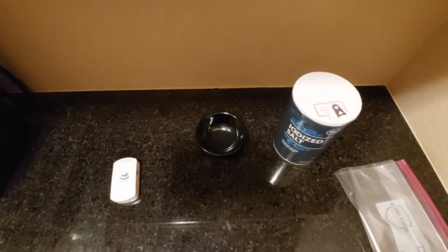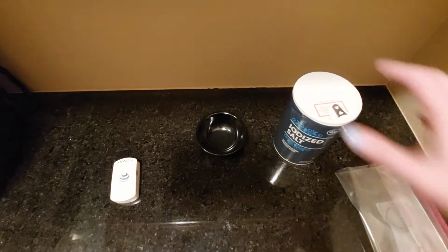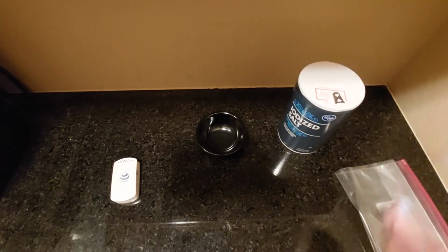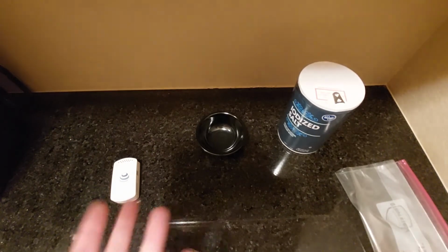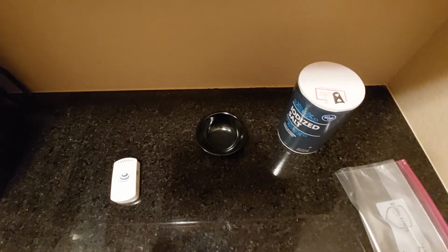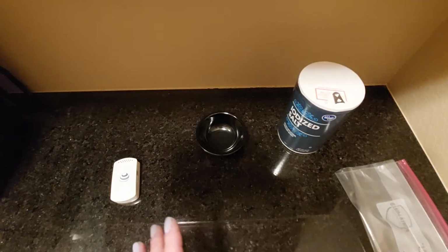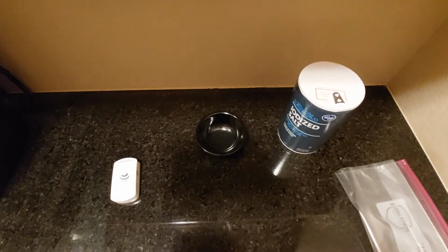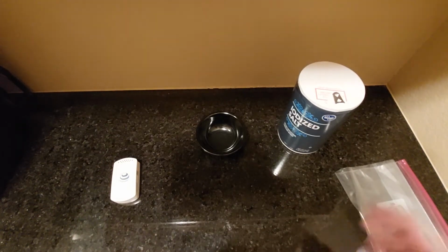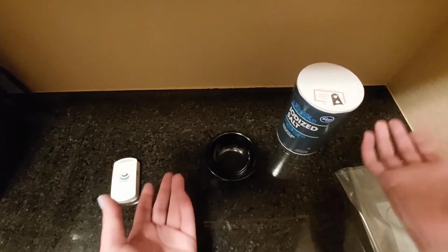So next we're going to review how to do a 1-point calibration test for relative humidity. Basically, we're just going to use iodized salt, sodium chloride, table salt. In most temperatures, it has a fairly stable relative humidity of about 75%. So this is a really good one to start with if you're just going to do one single test.